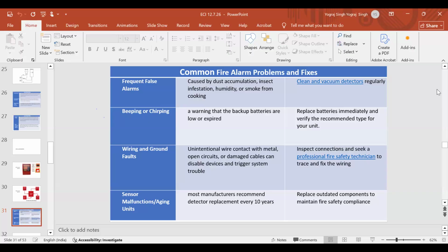So these detectors, which we saw in the previous slide, should be cleaned and vacuumed regularly. You have to engage an agency which does this and keeps a record of when each one was done, maintained properly. Beeping or chirping warns that backup batteries are low or expired. As I told, this fire alarm system will be fed from a UPS or a battery bank. As in the case of your torch, if the cell is low, it will glow faintly. So replace batteries immediately and verify the recommended type for your unit.